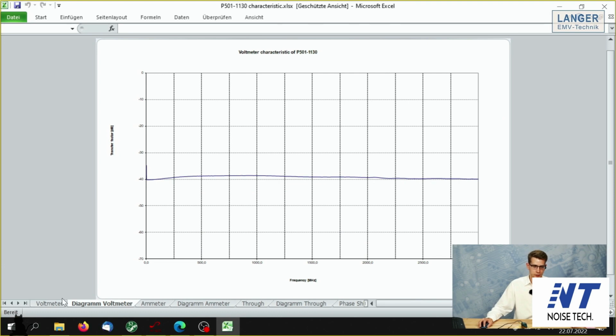So of course you then need to do a comparison of the curves. The curves are not allowed to differ more than plus minus 5% to be valid. And if it differs more than plus minus 5%, then the probe is not working and needs to be repaired or replaced.